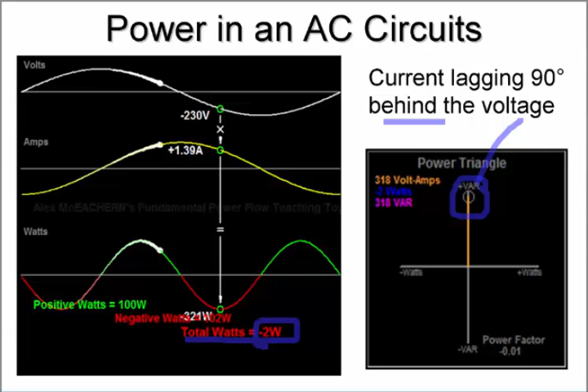The reactive component - this is a good example of what it actually is. If you buy a beer, what you're interested in is the liquid, but you end up with a lot of foam, which you don't really want and don't want to pay for, but you get it anyway. It's the same with reactive power. The municipality charges you for the full apparent power, not just the active power you use, so you want to get this foam as small as possible. That's why they put in power factor correction capacitors or other mechanisms to reduce the amount of foam - otherwise you'll have to pay for it regardless.